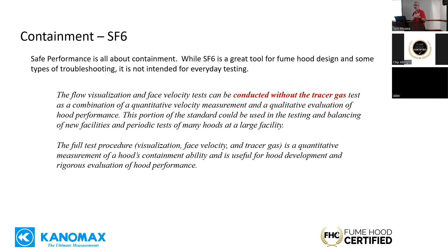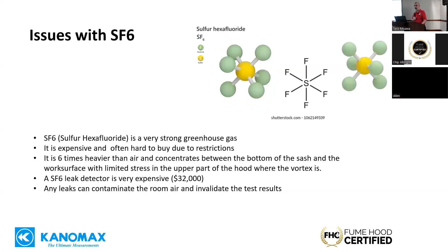So why are there problems with SF6? It's a very strong greenhouse gas. It's very expensive. In some places you can't even buy it. It also is 6 times heavier than air, and so the hood becomes much more concentrated down at the work surface. So you're not really fully testing the hood because it's coming out of the ejector and falling immediately down to the work surface. And then a leak detector is very expensive, $32,000 right now. And so any leaks that the hood has then contaminate your background. And so if there's any leakage while you're doing SF6 testing, it can literally take hours to flush the room out and start over again.